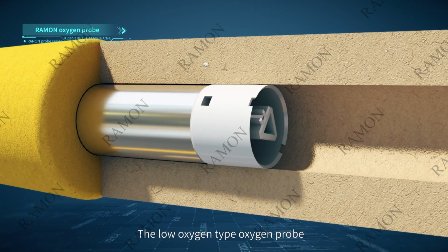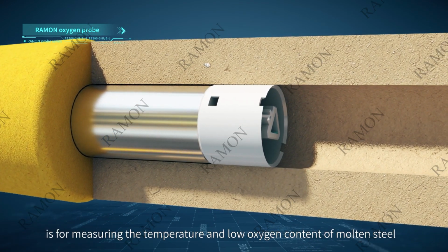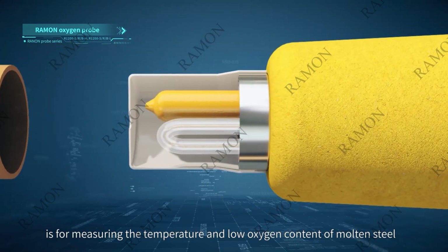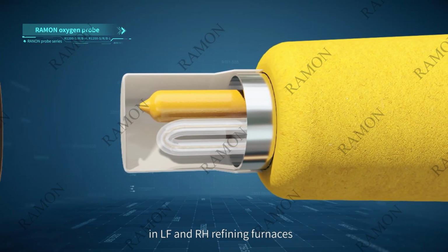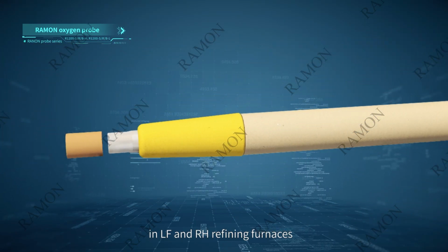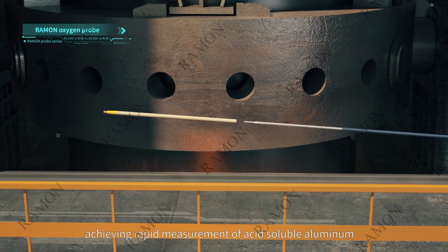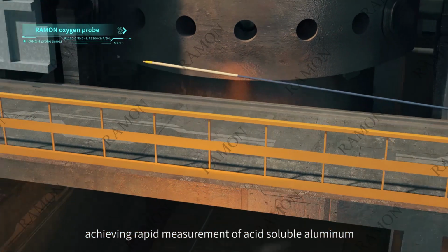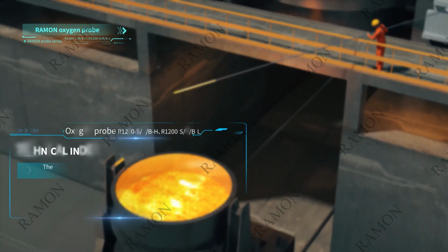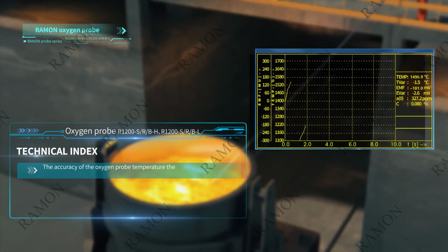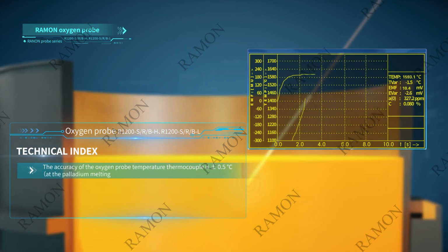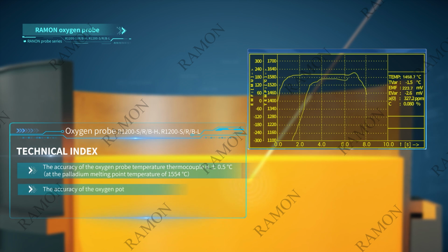The low oxygen type oxygen probe is for measuring the temperature and low oxygen content of molten steel in LF and RH refining furnaces, achieving rapid measurement of acid-soluble aluminum. The accuracy of the oxygen probe temperature thermocouple is plus minus 0.5 degrees Celsius. The accuracy of the oxygen potential is plus minus 3 mV, and the success measurement rate is larger than 98%.